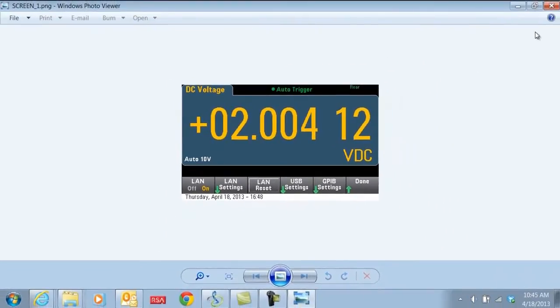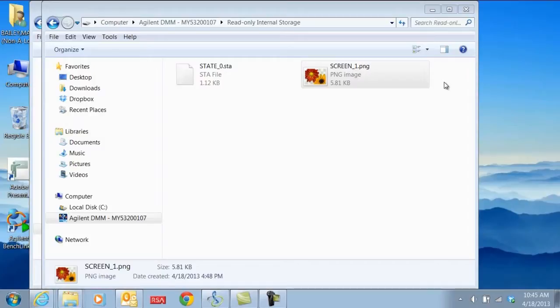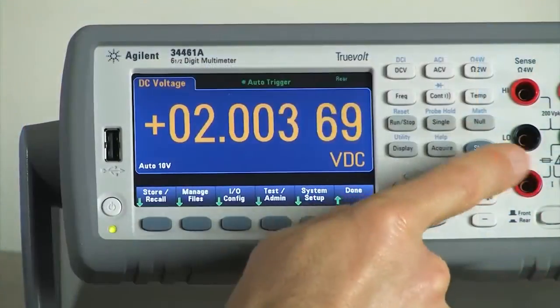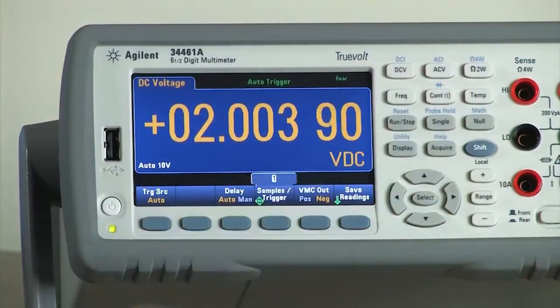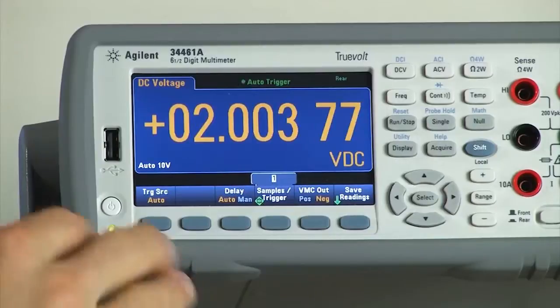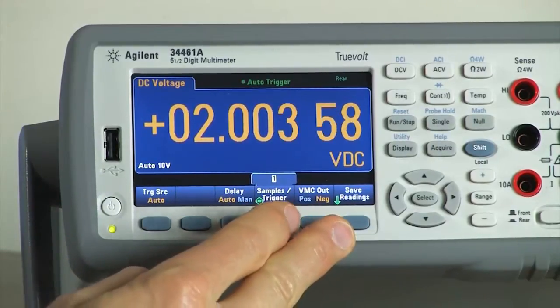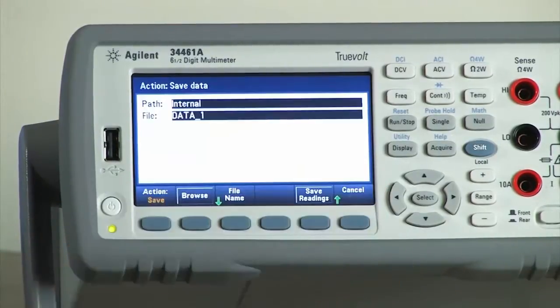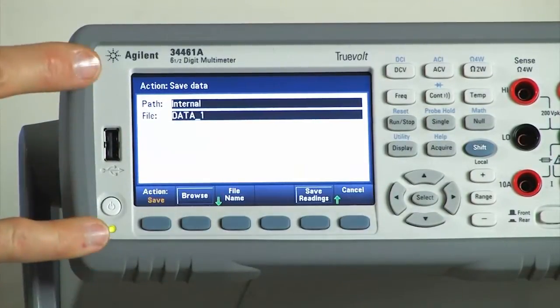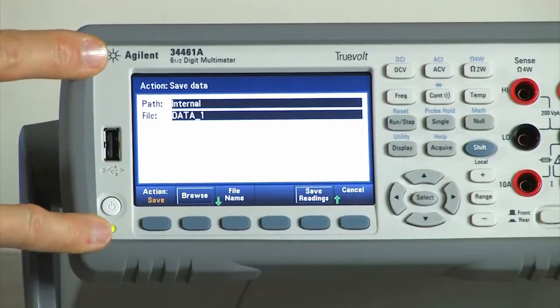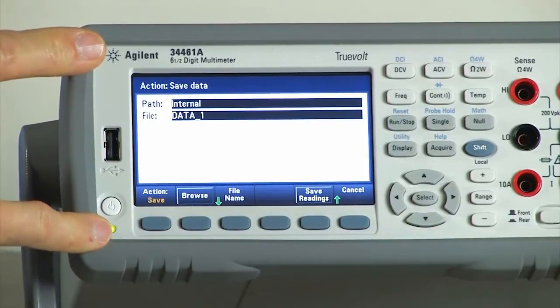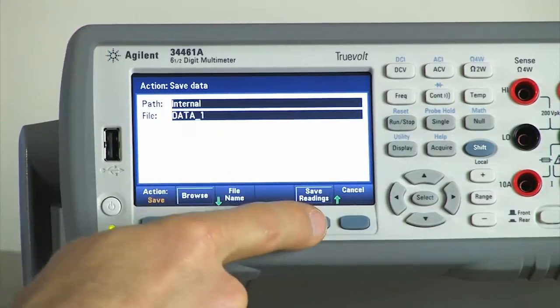Another common file type that we wish to transfer from the device is a CSV file or a data file. For that, we'll acquire, set up our triggering as desired, click Save Readings. Again, we can choose a new file name or use the pre-populated file name and then Save Readings.